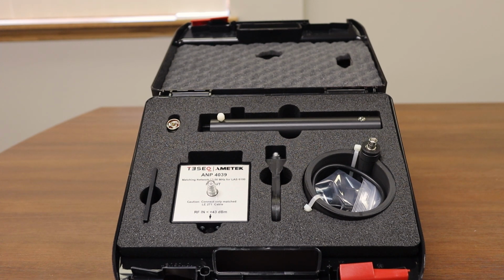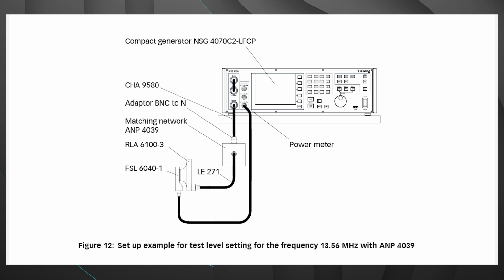Let's take a brief look at the setup in the user manual. We're interested in the setup for 13.56 megahertz today. However, I did do a previous video which covers a different frequency range, which I'll put a link for in the description below. Right now, we're looking at page 78 of the user manual at figure 12, which provides the calibration setup for 13.56 megahertz using our ANP 4039. We have the amplifier output on our test system going to the ANP 4039 matching network. From the matching network, we have the output going to our antenna, and then from there, we have the current probe connected to our power meter. Let's get the equipment set up and run the calibration.